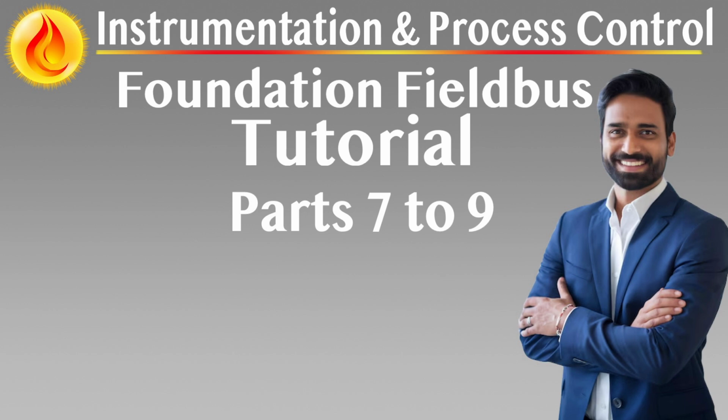Each VFD has a well-defined object dictionary, which includes indexed references to all parameters, block instances, data structures, and access rights. These indices allow deterministic access by hosts or other devices, regardless of manufacturer. Using this structure, configuration tools and asset management systems can reliably navigate the VFD, interpret parameters, and modify settings without requiring custom drivers. VFDs support both static and dynamic data, with real-time process variables updated on a schedule via publisher-subscriber communication and configuration parameters accessed asynchronously via client-server communication.